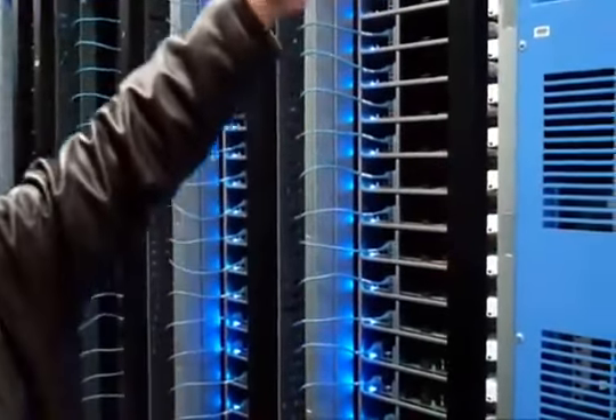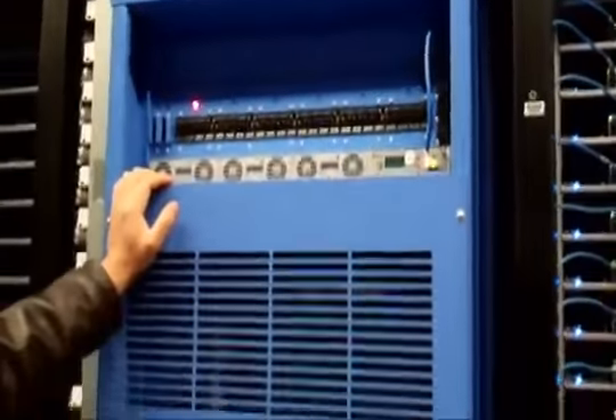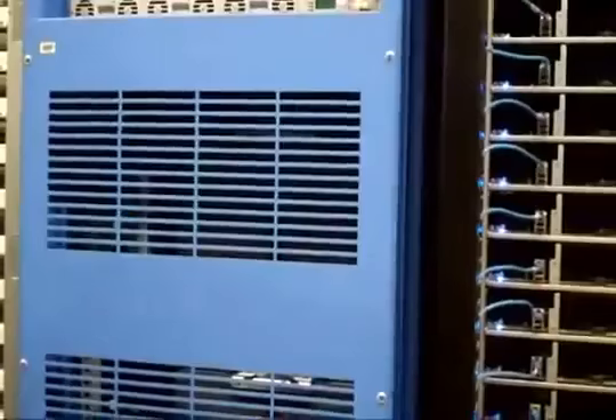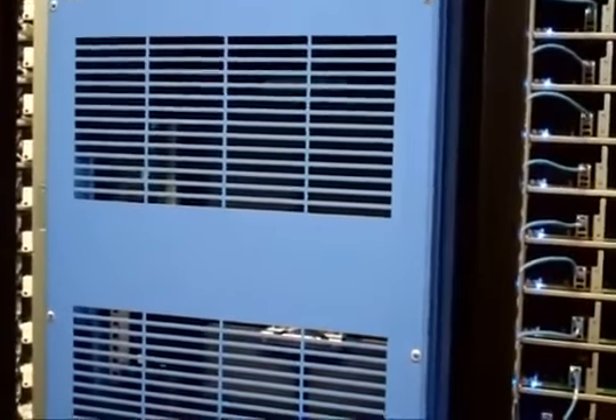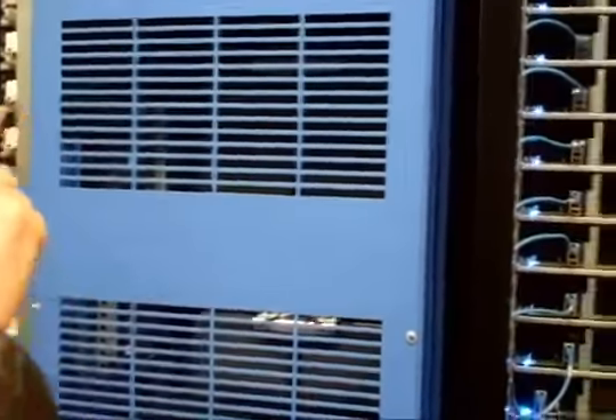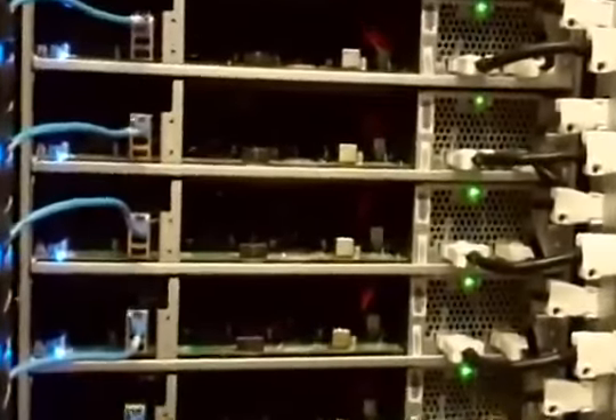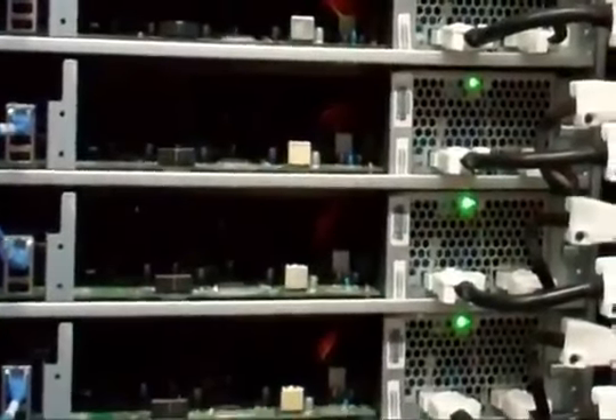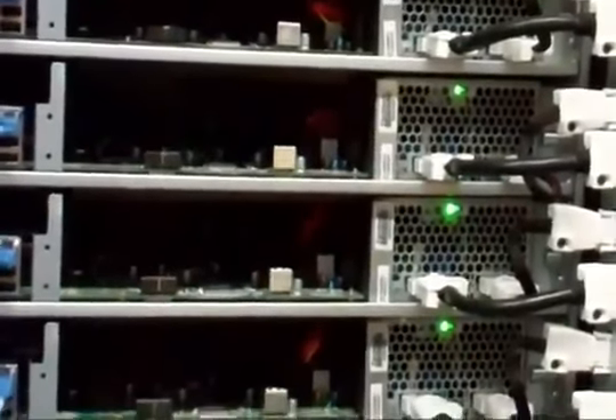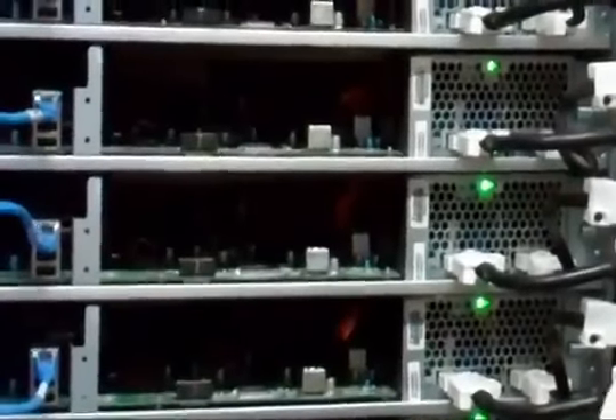So if you look at it here, all this thing needs is just a receptacle, the plug. It goes right up to that AC plug, and you're good to go. One plug. And then there are 6 DC cables coming out that feed each individual column. Those are all 48 volts, so it's safe. I wouldn't lick it, but it's okay to touch. It will not harm you at all.